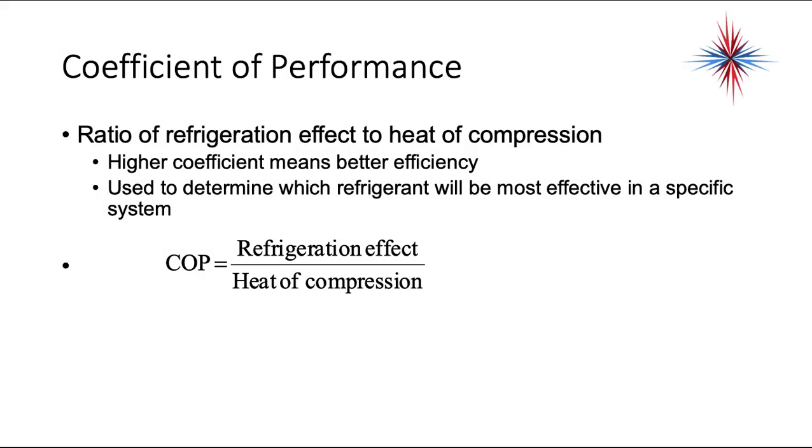The coefficient of performance is the ratio of refrigeration effect to heat of compression. A higher coefficient means better efficiency. It's used to determine which refrigerant will be most effective in a specific system. Coefficient of performance equals refrigeration effect divided by the heat of compression.